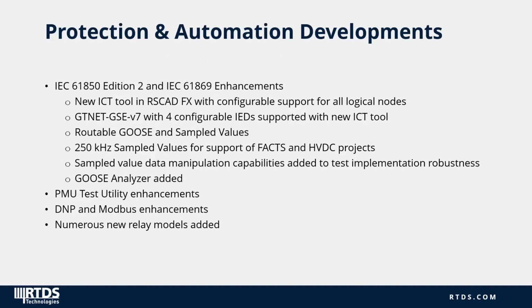There have also been considerable developments made in the area of protection and automation. Many of those relate to IEC 61850 or IEC 61869. A new ICT tool was implemented in RSCAD-FX with configurable support for all logical nodes. The GSE V7 firmware has 4 configurable IEDs supported with the new ICT tool. We've also added routable GOOSE and sampled value messages.